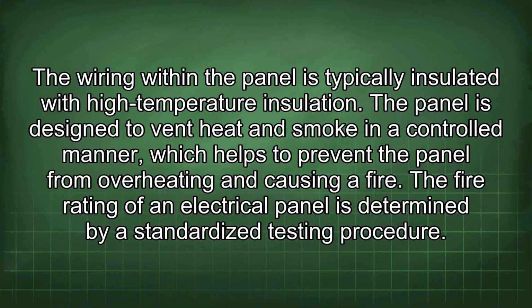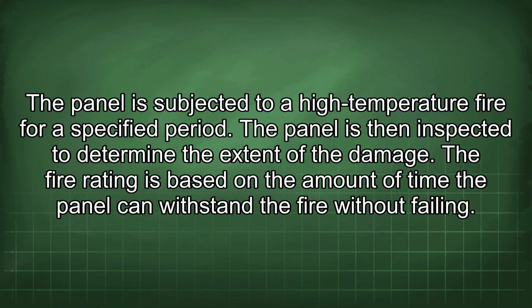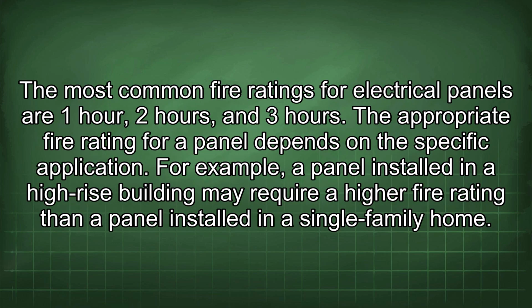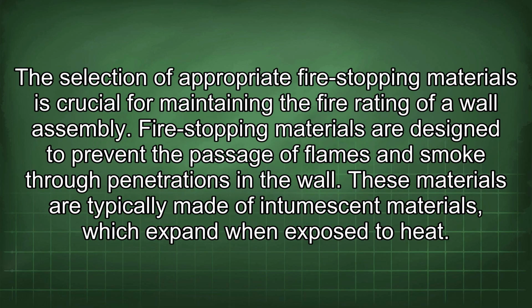The fire rating of an electrical panel is determined by a standardized testing procedure. The panel is subjected to high-temperature fire for a specified period. The panel is then inspected to determine the extent of the damage. The fire rating is based on the amount of time the panel can withstand the fire without failing. The most common fire ratings for electrical panels are 1 hour, 2 hours, and 3 hours. The appropriate fire rating for a panel depends on the specific application. For example, a panel installed in a high-rise building may require a higher fire rating than a panel installed in a single-family home. The selection of appropriate fire-stopping materials is crucial for maintaining the fire rating of a wall assembly.